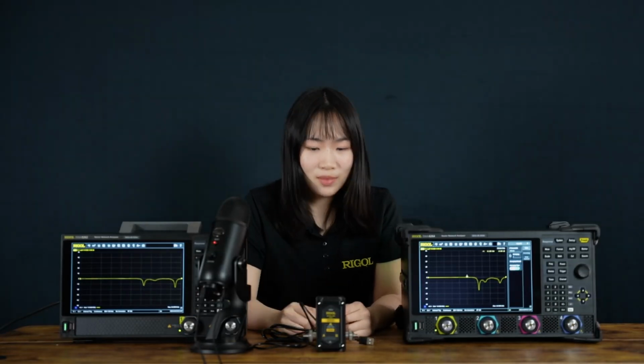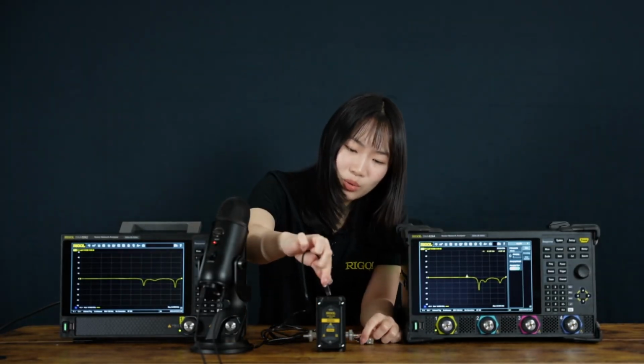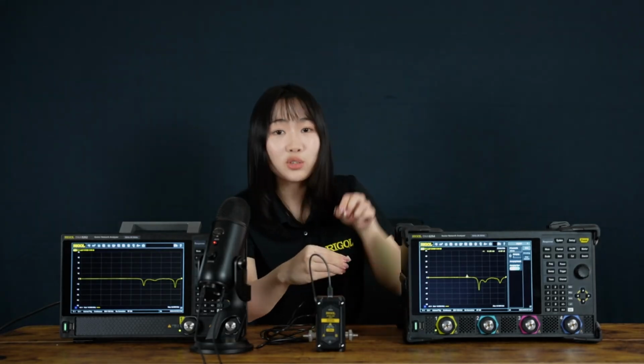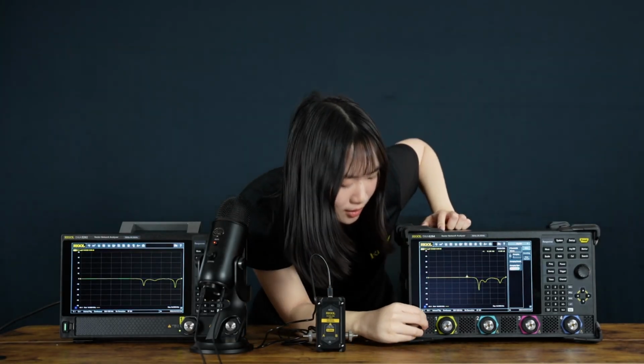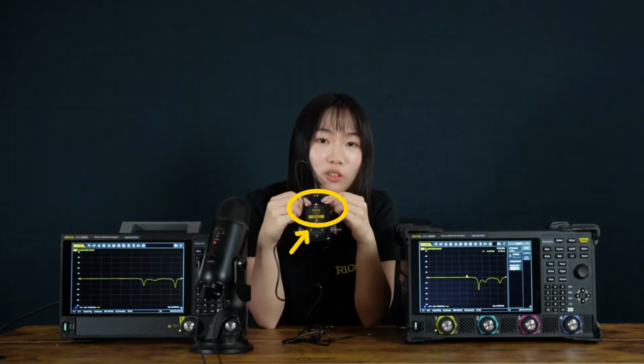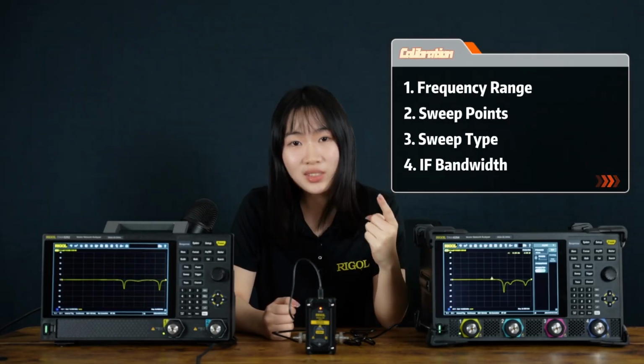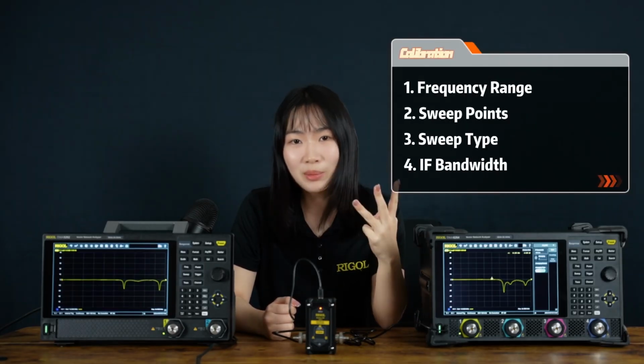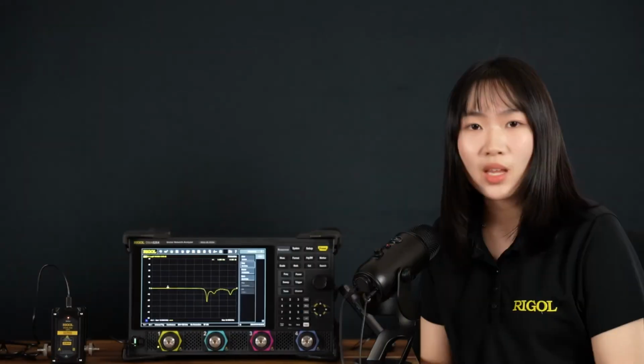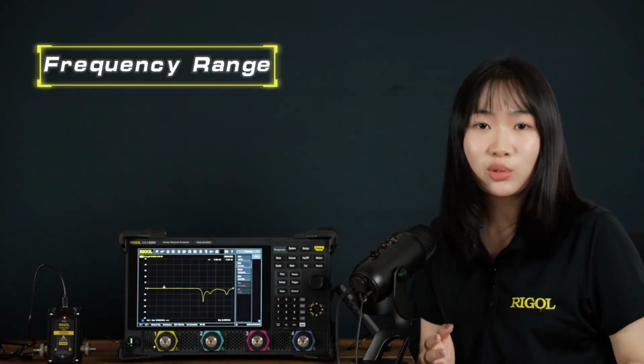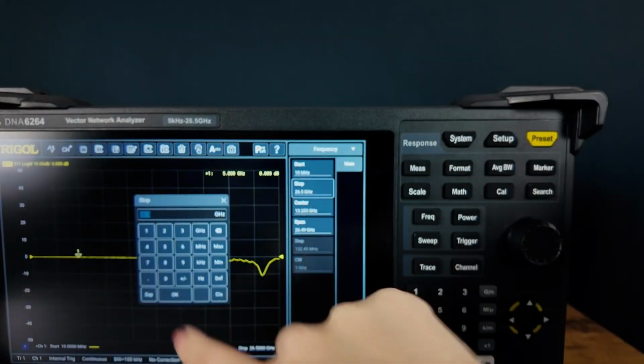The first thing to do is connect the ECal module with the USB-C cable. ECal usually needs a preheat period. That's about 10 minutes. And once that's done, the status light will turn from red to green to show it's ready. While that's warming up, there are a few things to set before calibration: frequency range, sweep points, sweep type, and IF bandwidth. For frequency range, match it to the device you are testing. For example, if you're working with a 3 GHz low-pass filter, you can set it from 10 MHz to 5 GHz.